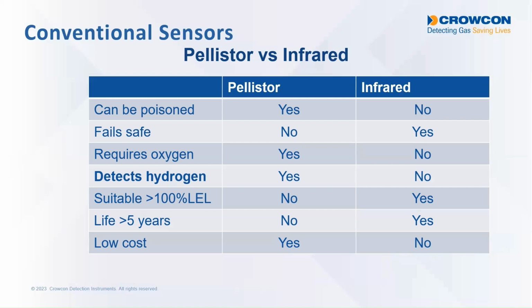Pellistors also require oxygen to work, so they can't be used in oxygen-reduced atmospheres, whereas infrared sensors don't need the oxygen to work, but pellistors detect hydrogen and infrared sensors don't. So for the purpose of this presentation, infrared sensors are pretty useless because it will detect methane, but it won't detect hydrogen. Pellistors also are designed to work up to 100% LEL. If ever exposed to gas concentrations above, then there is a risk that the pellistor will actually burn out and will need replacing, whereas infrared sensors won't be harmed by exposure to high gas concentrations.